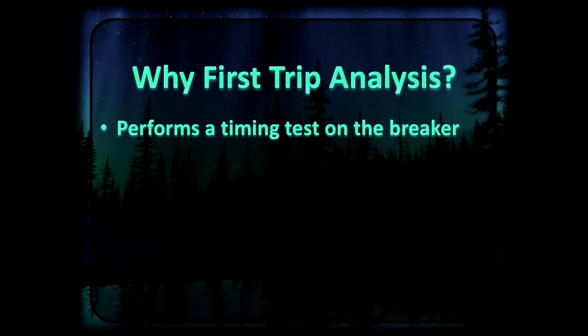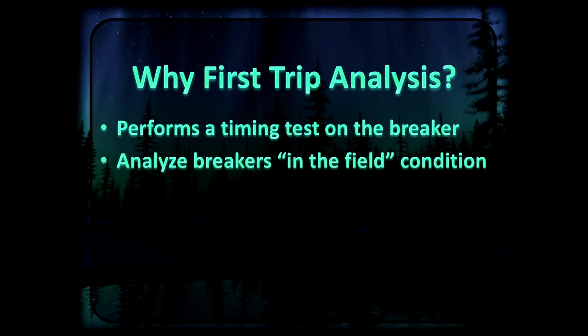The benefit of doing a first trip analysis is that it analyzes a breaker in the in-field condition. Most of the tests that we do on breakers, you have to take the breakers out of service, which means you have to operate them, open them, open up switches on each side of the breaker, isolate them, and then you're able to start your tests. With this test you're able to do it while it is live, and you get a real-time analysis of how the breaker will perform.